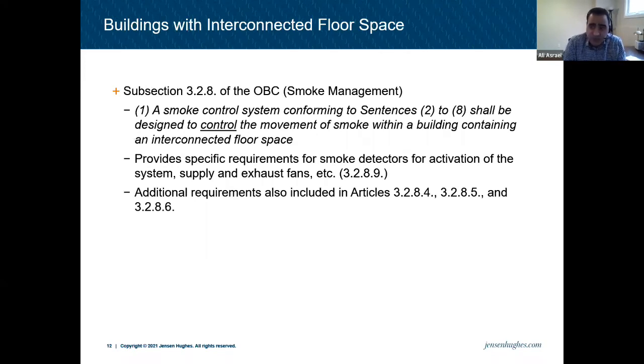There is another area in the building code, subsection 3.2.8 of the OBC, talking about smoke management. It is a smoke control system conforming to sentences 2 to 8 that shall be designed to control the movement of smoke within a building containing an interconnected floor space. So technically, we'll be having interconnected floor space. Then at that point, you need this smoke control system or smoke management system.